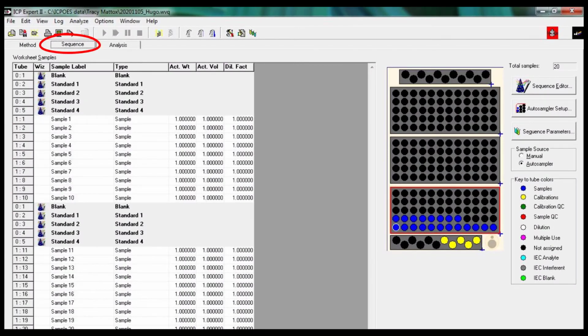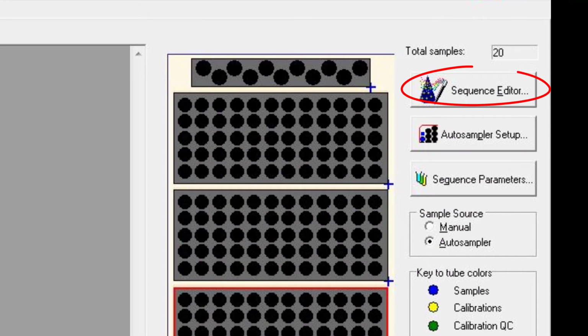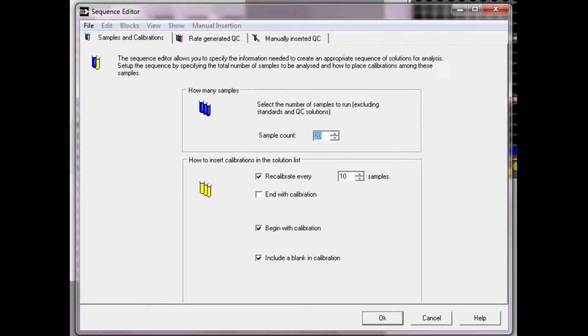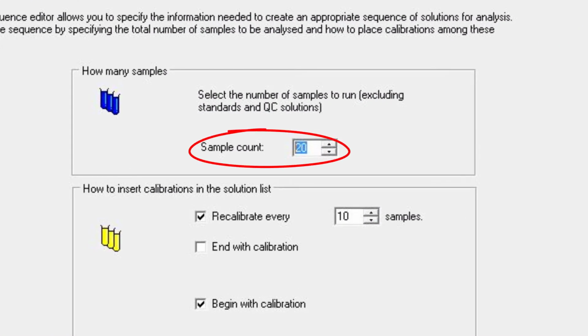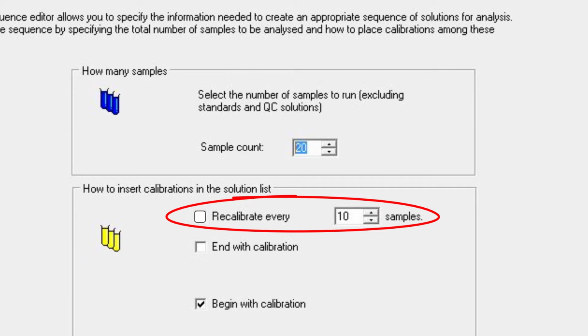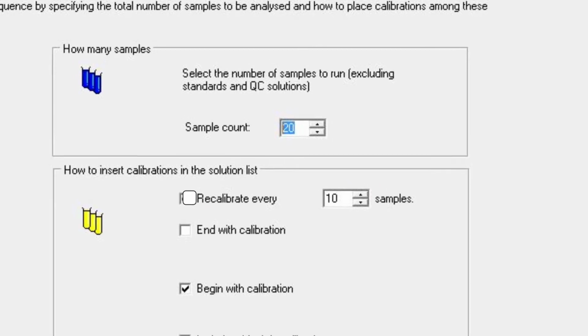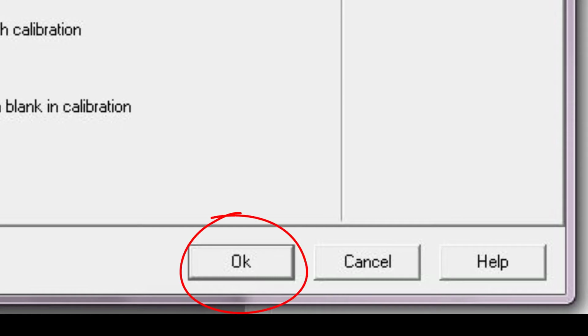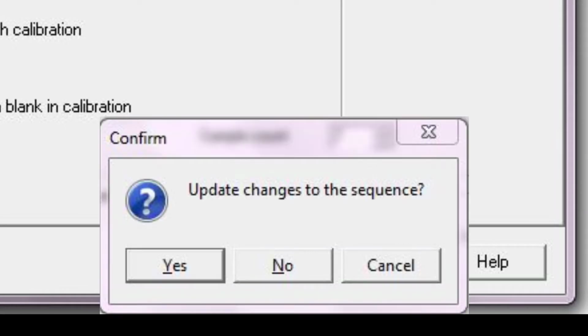Click on the Sequence tab to continue the setup. On the right-hand side, press the Sequence Editor button. Enter the number of samples you will be running. This does not include the number of standards. You can also uncheck the box requiring recalibration every 10 samples. Most people don't recalibrate this frequently. Press OK, and in the pop-up window, press Yes.